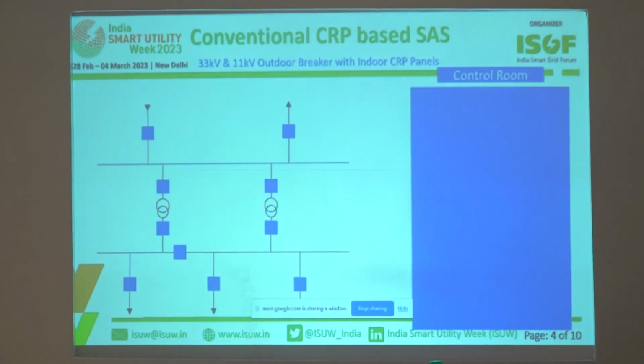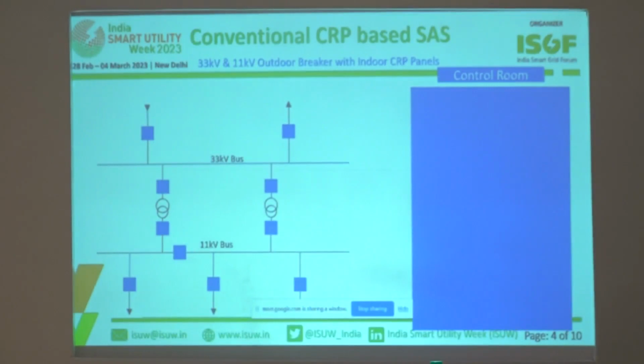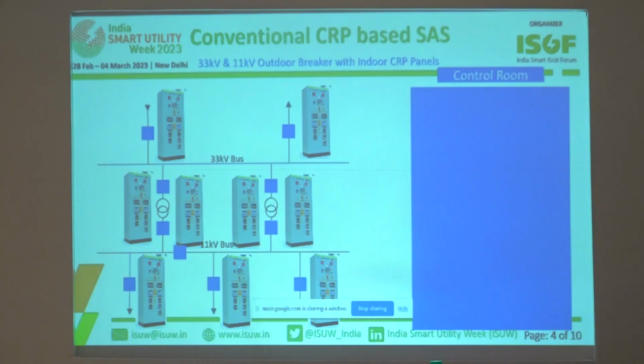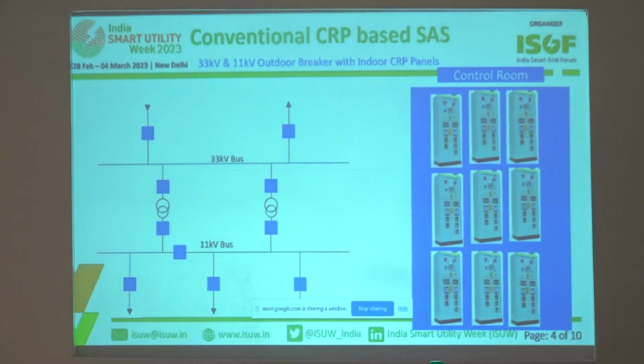The conventional CRP based approach - I would like to show here. There is a 33 by 11 kV substation, on the 33 side one line incoming, one outgoing line, and 2 transformers. This is a typical scenario we are facing in our Western Odisha area. The control room has CRP panels, and all these CRP panels are placed in one control room. This requires a huge control room size, as well as laying so many cables. We need cable trenches as well as an RTU to be installed to make it communicable.